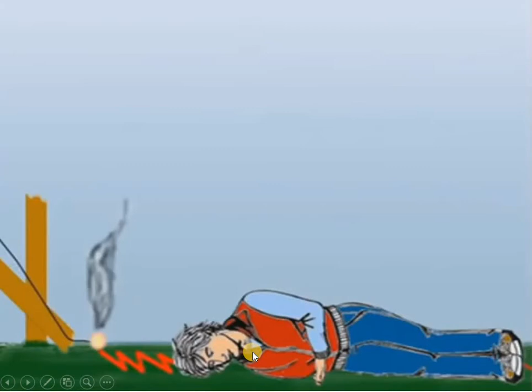When a fault occurs, fault current flows to the ground, causing a potential gradient to develop near the electrical equipment. This potential gradient can affect a person in two ways: either through step-to-step contact or through touch contact. The previous diagram illustrates step-to-step voltage.